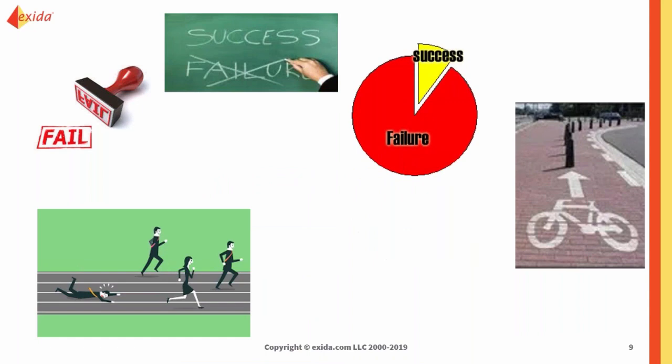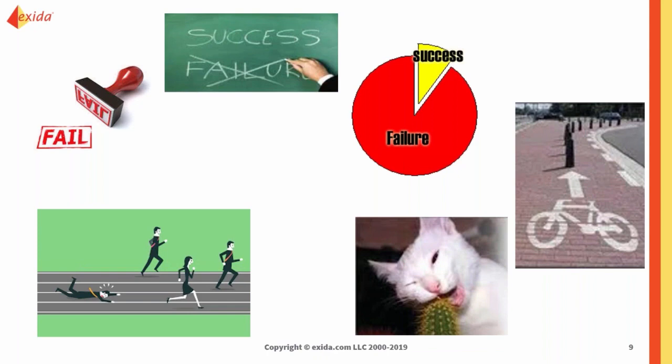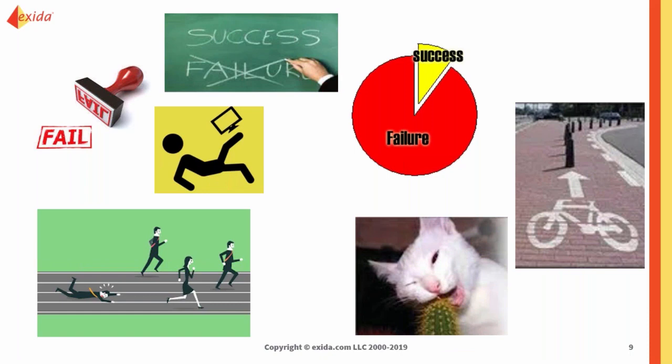It's usually considered a constant value because of the bathtub curve and other statistics like that. It can be broken down into both safe and dangerous categories. Those safe and dangerous categories can also be further broken down into detected and undetected. They can be looked at as independent or normal, or even common cause failures.